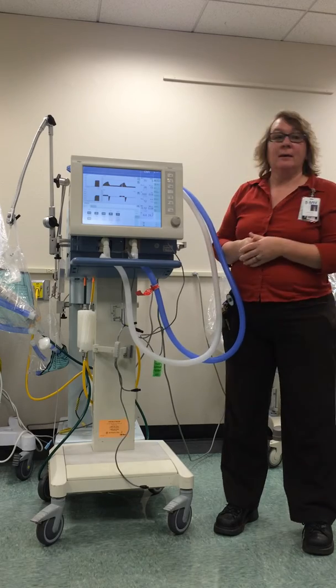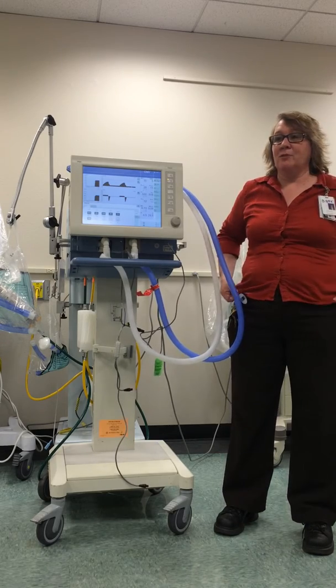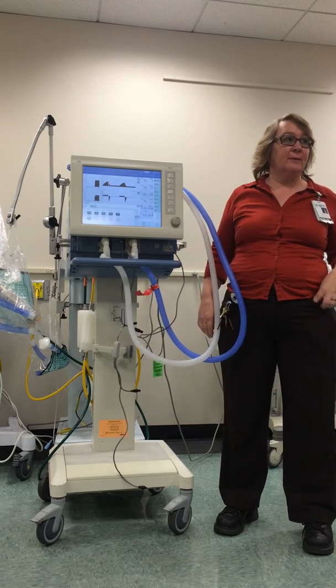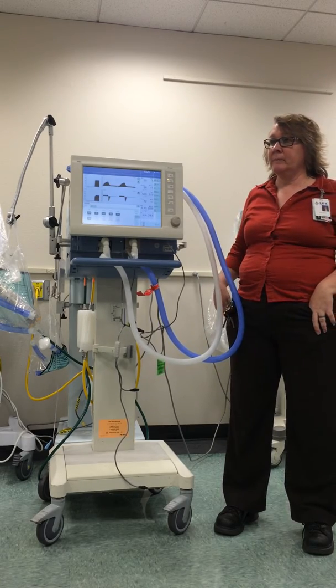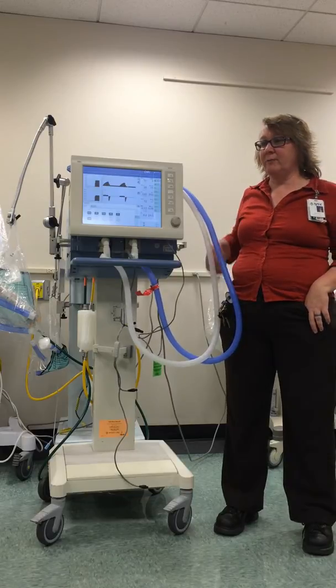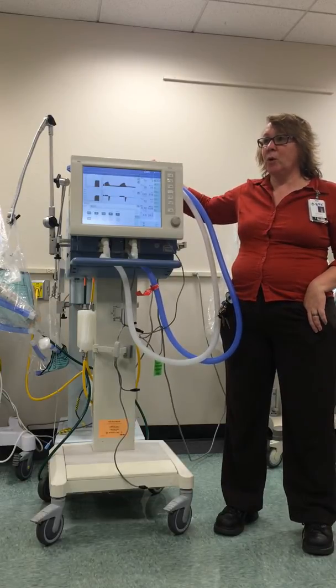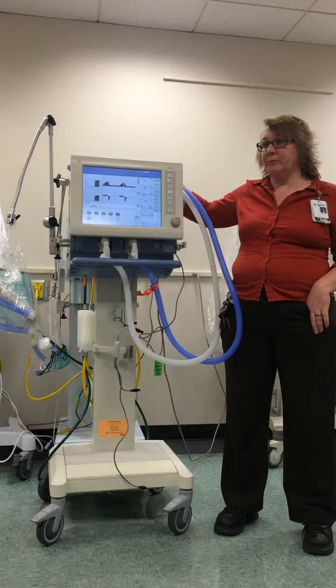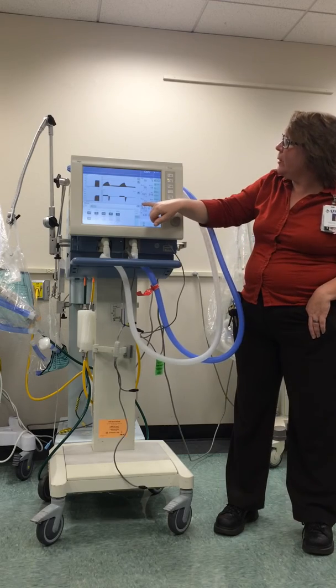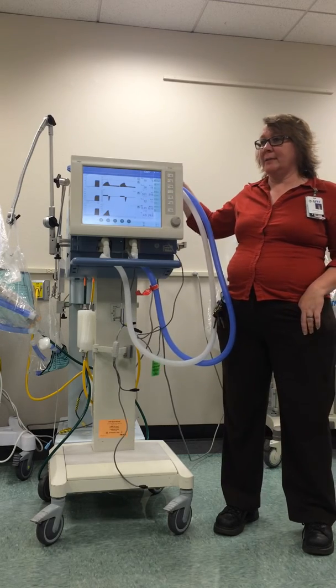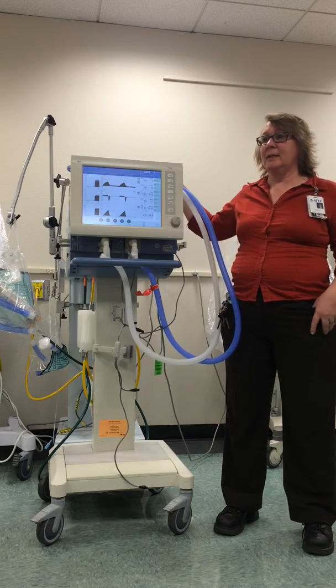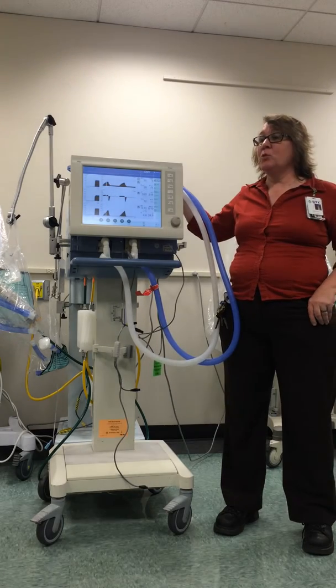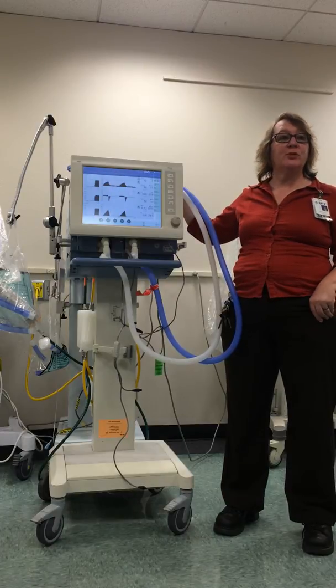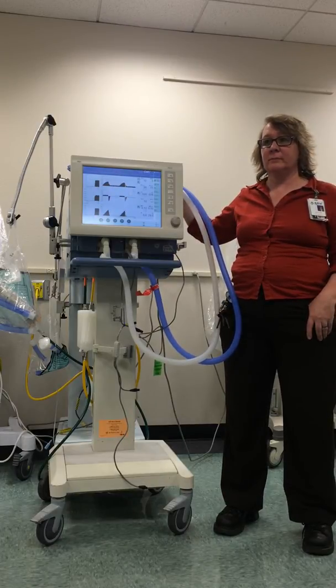And then apnea should be at 20 seconds. So if my patient is apneic for 20 seconds, the ventilator will kick in and give a breath. For CMV? No, apnea is for all of them, for everyone. You technically could put CMV of 4, and your patient could go apneic and not breathe. That's why it's there. Some of them have it, and some of them don't. But you can still set too low of a rate, is what I'm saying. And if your patient's not breathing on his own, then it would kick in. What is the minimum? 20 seconds. Yes. If you have an opportunity to set an apnea alarm, set it at 20 seconds. That's standard.